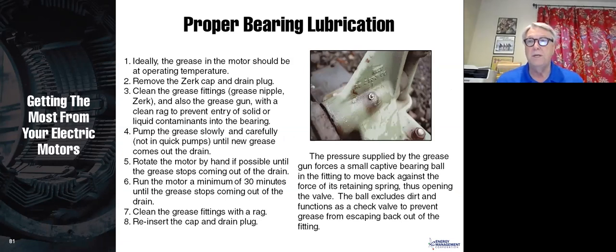So this is, in general, a good recommendation for how to grease a motor. Number one, ideally the grease in the motor should be at operating temperature. You can't do that all the time, but it would be really great if you could shut a motor down while it's hot and grease it right then. Number two, remove the Zerk cap and the drain plug. Number three, clean the grease fittings.